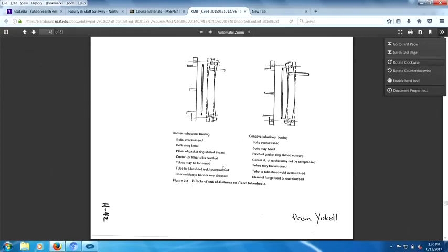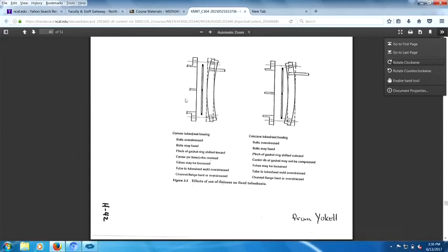So whenever you're talking about tightening your bolts on your tube sheets, your flanges. So you have your flange here. You could possibly under-tighten, where you could possibly bow your tube sheet in such a manner that the tubes expand and you haven't got them tightened up enough. And then this is convex, overstressed.